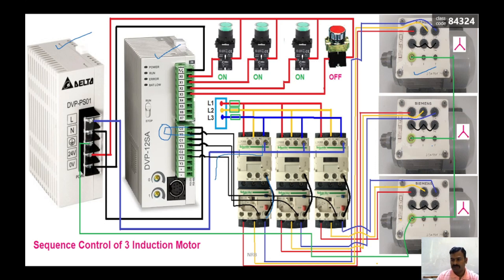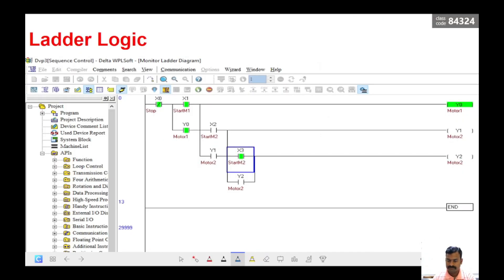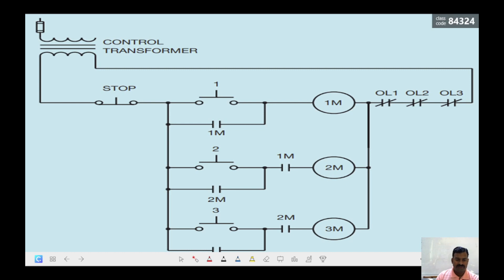Likewise, the second and third motors get connected in sequence and the respective motors run. At any point the stop button can be operated, and when it is, the ladder logic turns off all the contactors so the motors go off. This is the ladder logic for the given circuit, which we will see in the simulation. The same problem can also be solved in a different way — this is another control circuit with the same number of switches and coils but arranged differently.